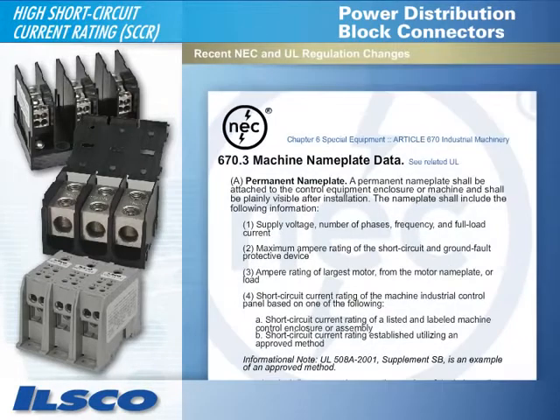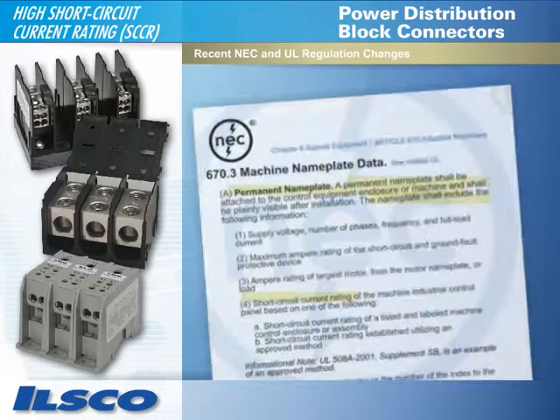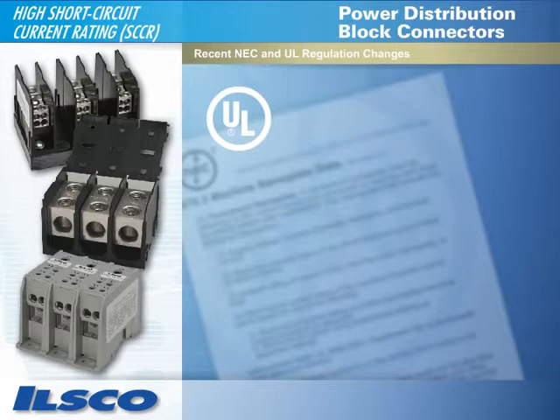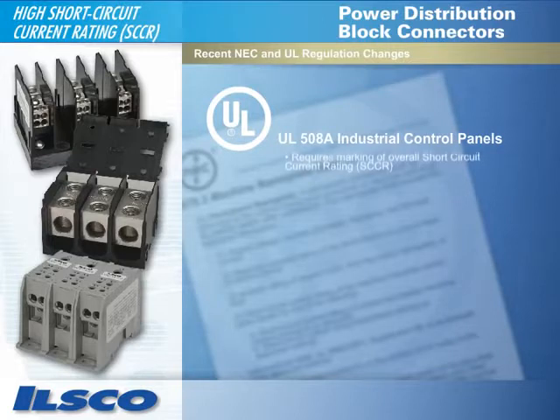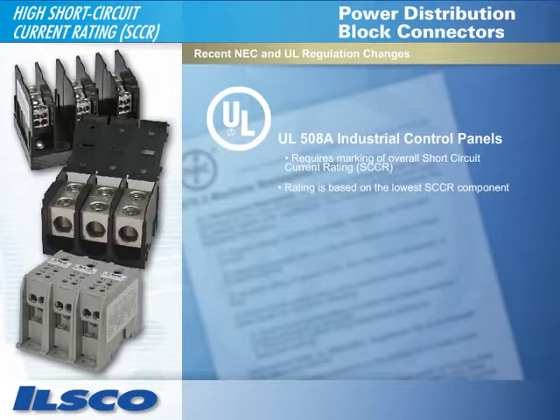Recent changes to the NEC require nameplates on industrial control panels and industrial machinery electrical panels to now include the short-circuit current rating. In response, Underwriters Laboratories modified UL-508A, its standard for the construction of industrial control panels, to require marking of the overall short-circuit current rating, or SCCR, of an industrial control panel.